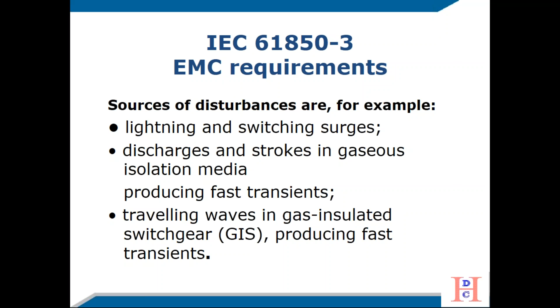And here's the shopping list of standards, the ones in black are those that were already there, augmented by the ones in red, the 4-X series as you can see. The good news is most EMC laboratories already do the large share of these measurements, if not all, in black. Maybe they don't get into surge withstand, or DC and AC power port testing with voltage dips and interruptions. That's not to say you may not have special needs requiring that, but I consider this good news, because typical EMC laboratories probably already do two-thirds or more of these tests.